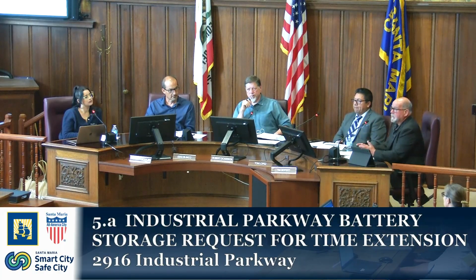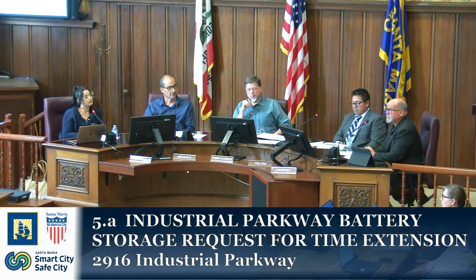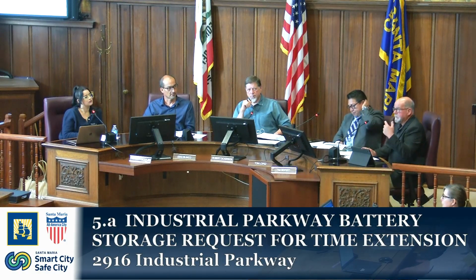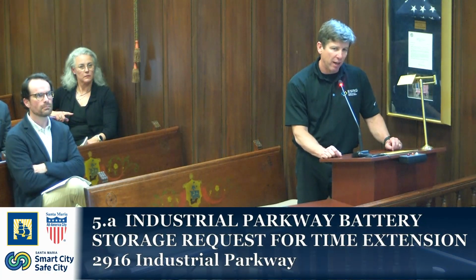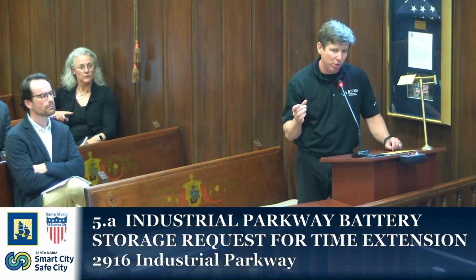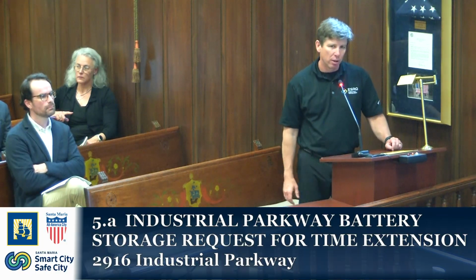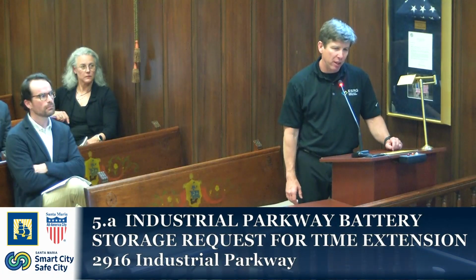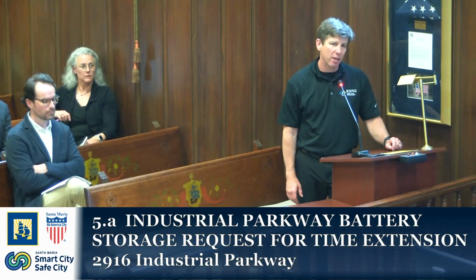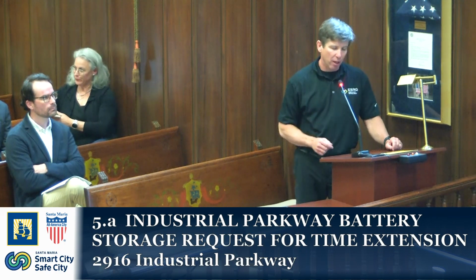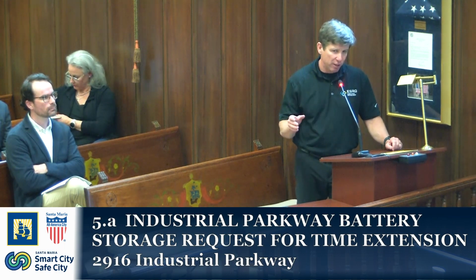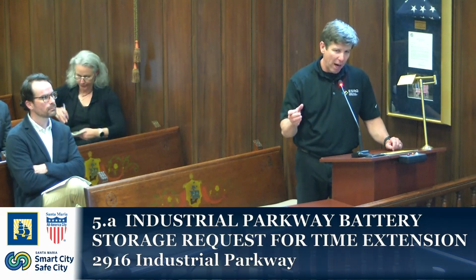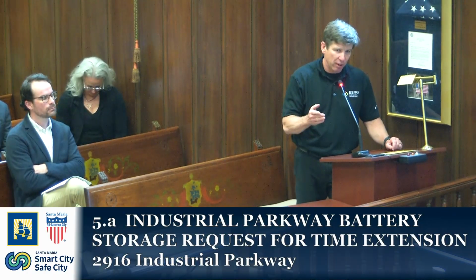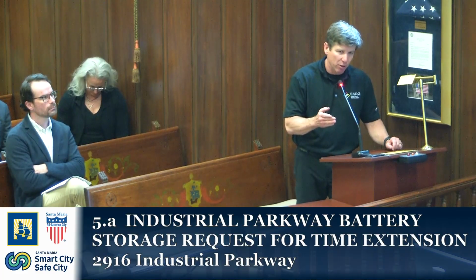That's so that - if I'm not mistaken, the fire is going to start with one cell. Correct. And then that cell is going to generate heat, and it's going to get the cell next to it that had nothing wrong with it? Well, it shouldn't. They're designed now so that it should end with that one cell and not propagate to the other cells. Because of this new battery technology? Because of the battery technology, and that's what the testing in UL 9540A actually tests - they test driving a battery cell into runaway to see if it propagates to neighboring cells.